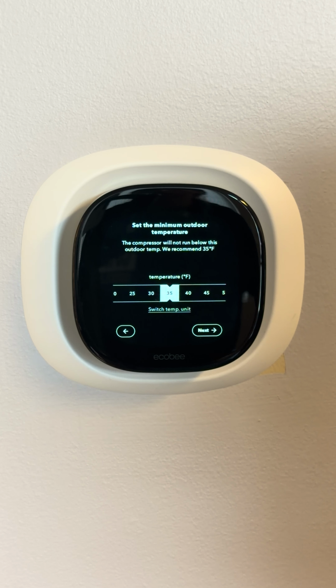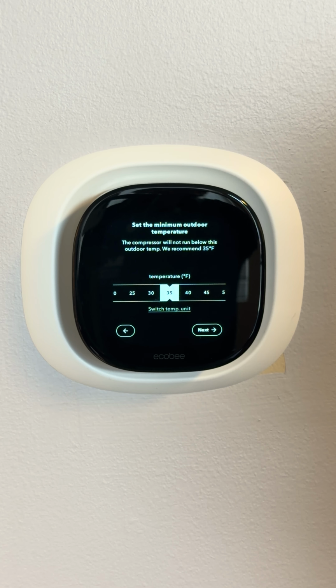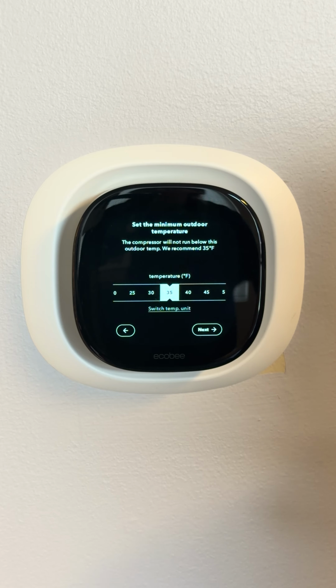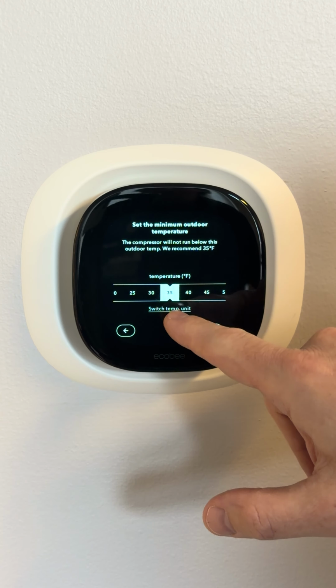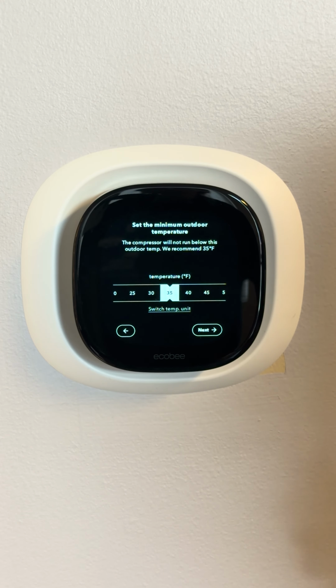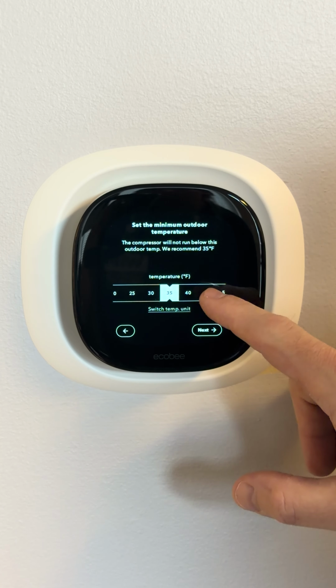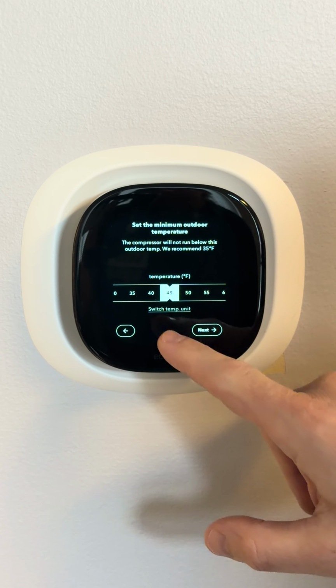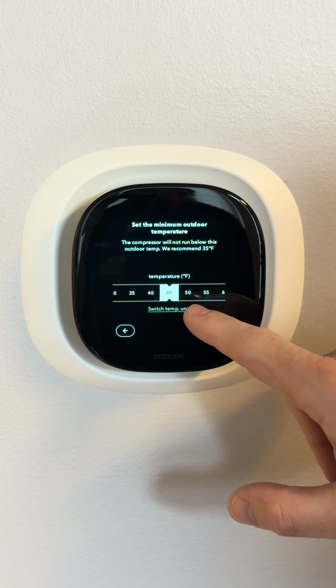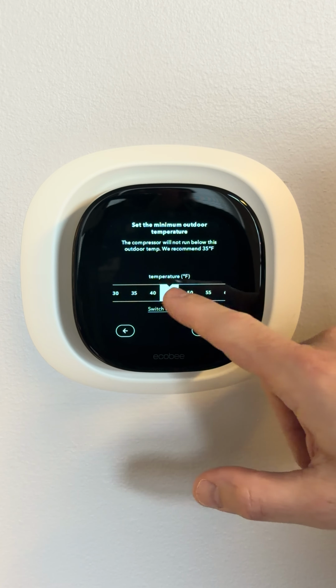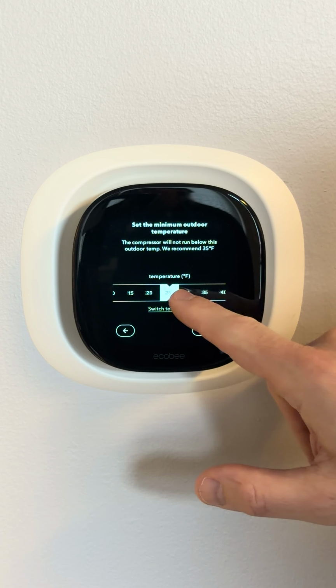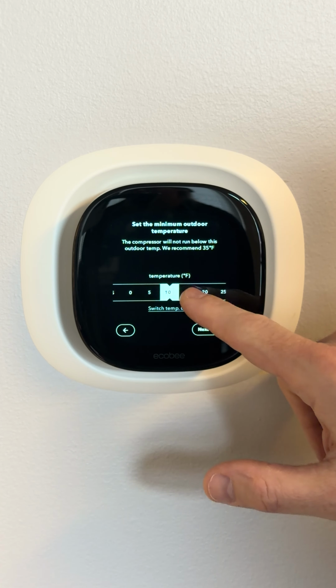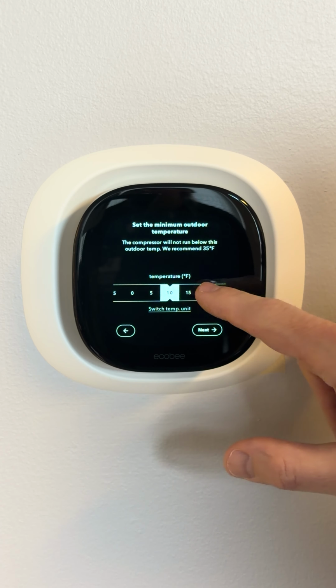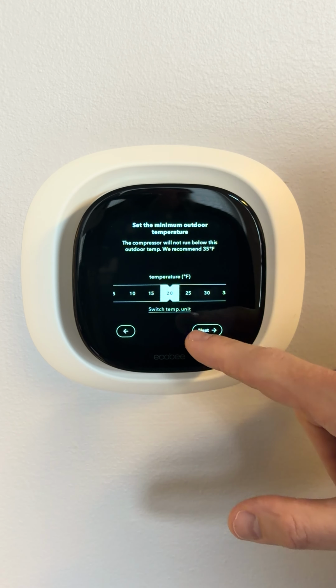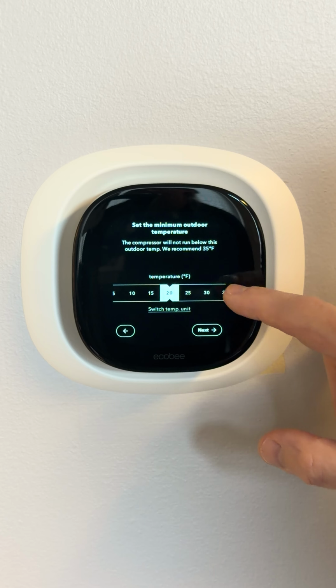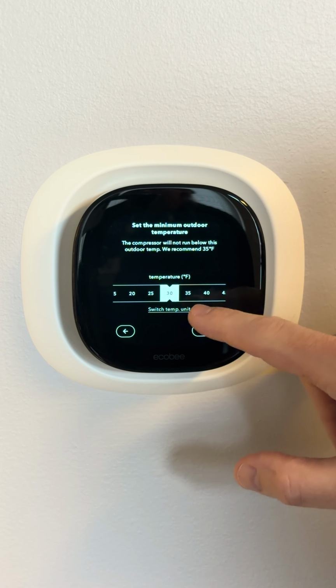And then this is the temperature at which the condensing unit outside will shut off. So it's defaulted at 35 degrees for almost every installation. That's going to be fine. If you want to increase the comfort inside the house, you can increase that to 40, 45, or 50 degrees. If you have a cold climate heat pump, you can bring that all the way down to whatever you're comfortable with. And that will maximize any possible energy savings you can get from your high efficiency heat pump. And it'll let the two of them run together.